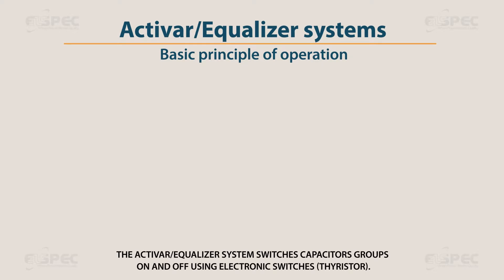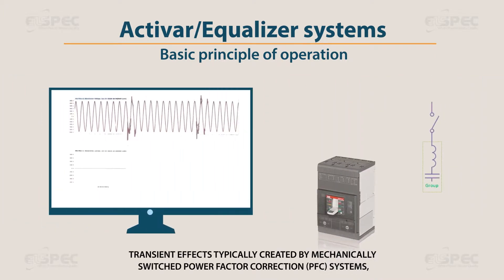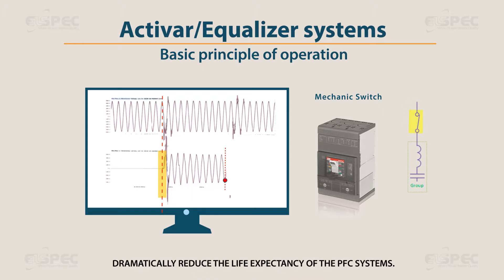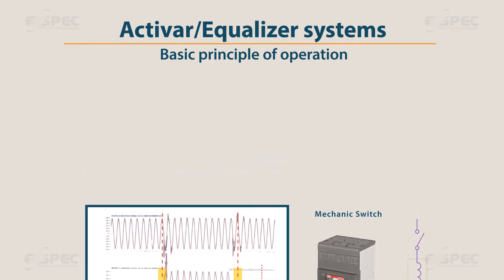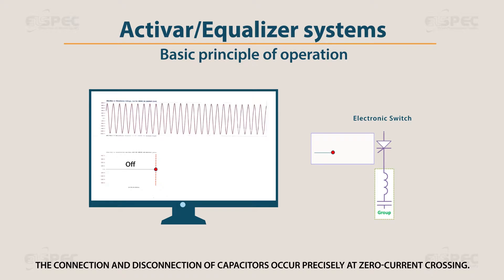The ACTIVAR equalizer switches capacitor groups on and off using electronic switches — thyristors. Transient effects typically created by electromechanically switched power factor correction (PFC) systems dramatically reduce the life expectancy of the PFC systems. The advantage of the AC-EQ systems is that the connection and disconnection of capacitors occur precisely at zero current crossing.